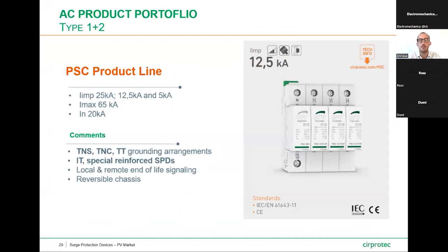It is our PSC product line. We have solutions with an Iimp of 25 kA, with 12.5 kA, and with 5 kA as well for specific PV applications. We are declaring for the type 2 test an Imax of 65 kA and an In of 20 kA. This product range is suitable for TNS, TNC, and TT networks, as well as for IT networks with special reinforced SPD solutions that can also be applied for PV applications close to the inverter. We have solutions with local and remote end of life signaling, and the cartridges are reversible to be sure we are fitting whatever installation requirements our installers have.